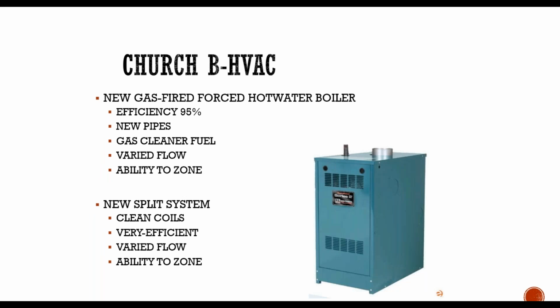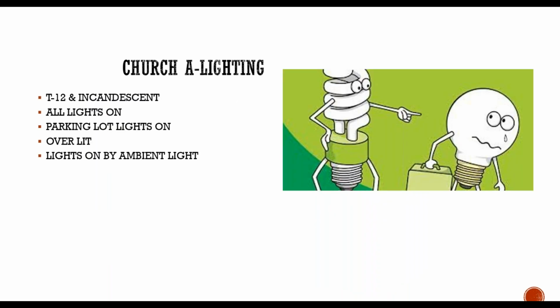So if you have an older oil-fired steam system, you're looking at a unit that might be 50 to 60% efficient right off the bat. Pipes are old, they leak, and oil on average is 3 times the cost of gas. It's also constant volume, which means if you want to heat just one room, you have to heat the entire building. On the 20-year-old split system at the bottom, you see those coils are crushed in. I see this all the time, and this is a behavior thing. If up to 10% of the coils on a cooling system are bent in, and I encourage you to go look at them, you can lose up to 30% of the efficiency of that unit. Wow. Okay. All right. Go ahead.